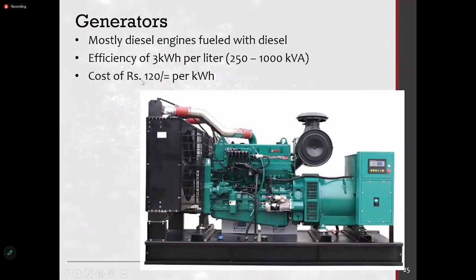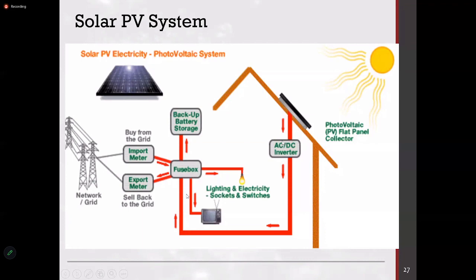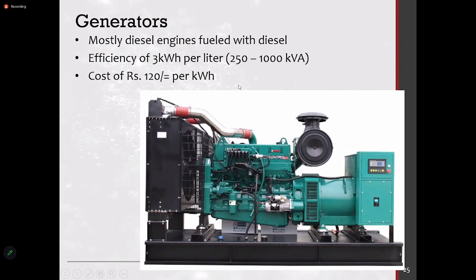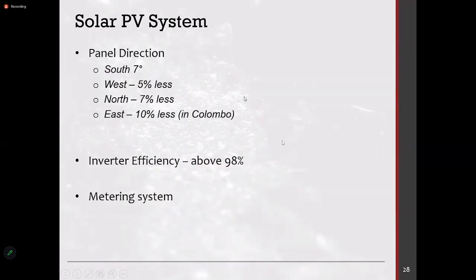So the advantages are these numbers. Without running the generator, if you do this, even with the 20% loss, you can still supply your system. A lot of installations had very high capacity on-grid systems, but they were struggling during power failures, where they couldn't run the solar system. The solar is generating, but you can't use it for your own requirement, or export it, because the grid is not available. So you have to run the backup generator. Now you are allowed to have a backup battery system with a hybrid network, where you can store the solar energy and use it during a power failure. If there is a further power failure, then you can switch on the generator, whereas this cost is drastically high.